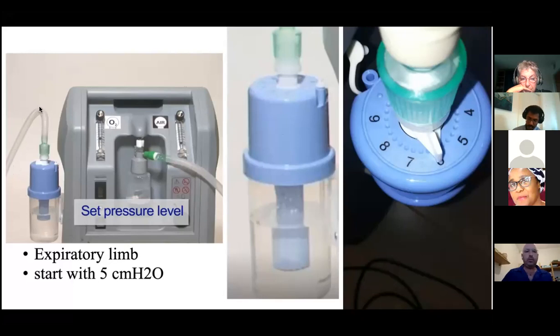We have the expiratory tube, which is connected to the CPAP bottle. This is where you connect it to the Diamedica machine on the side. And the pressure of the CPAP is determined by the depth of the tube that is immersed into the water. We use the water pressure to produce the positive pressure.